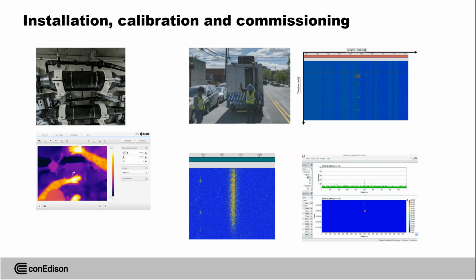There's a picture of the complete system from substation side. You see the rack with partial discharge, DAS, and all other systems. You can come here, you can log in, you can get all information from there. You can see live feeder, infrared on the bottom picture. You see this is from infrared camera. You see now it's a different color because it's a different temperature, and you see supports have a higher temperature than basically cable itself. And this is a video how you see from video camera for inspection. You see water covering almost like half of the bottom cable. You can see all support from one side and from another.